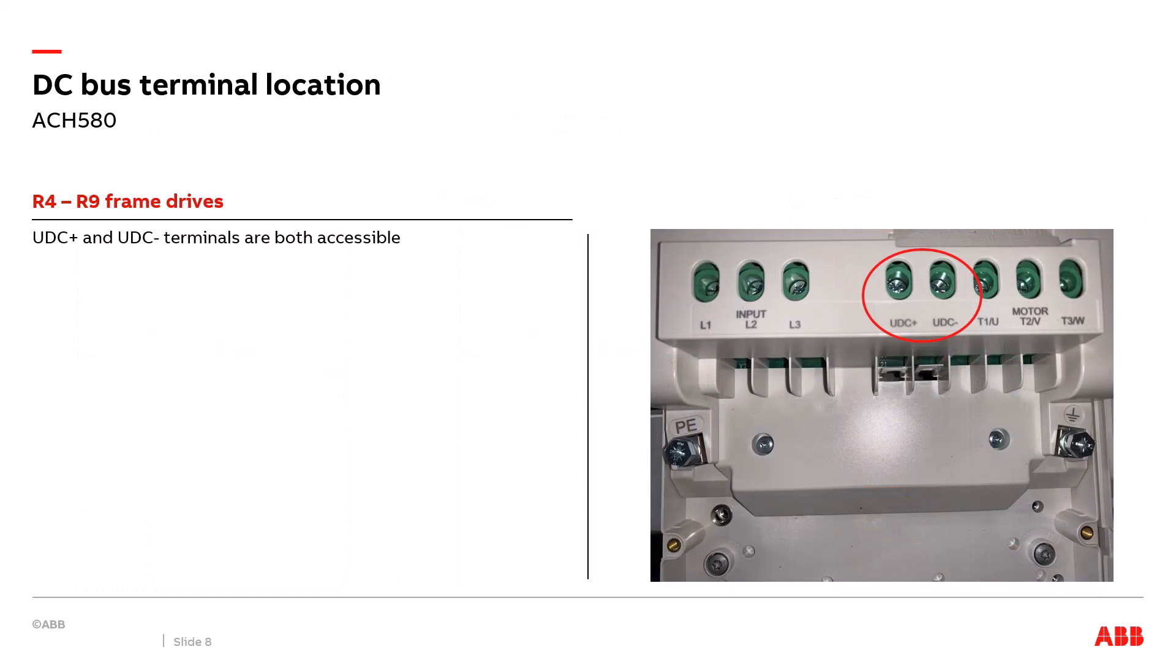On larger horsepower drives access to both the positive and negative DC bus is usually easier. On the 580 series they include the R4 through R9 frame drives. Access to the UDC plus and UDC minus terminals are both right next to each other as shown in the red oval in the image on the right.